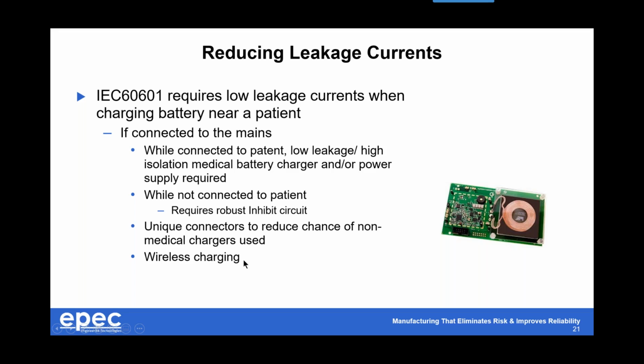Another thing that's really come into play recently, over the last 10 years, is wireless charging, and they're upping the wattage. Now I think they're in the 10, even 15, 20 watt range, which is really nice because there's inherent isolation and inherent low leakage - there is no leakage, because they're essentially an air transformer if you really think about it. Wireless charging is a great option. You can waterproof your products, and you don't need to have connectors. It's something really worth looking into, depending on the environment you're using your medical battery in. But that's something we can easily put into a medical battery.